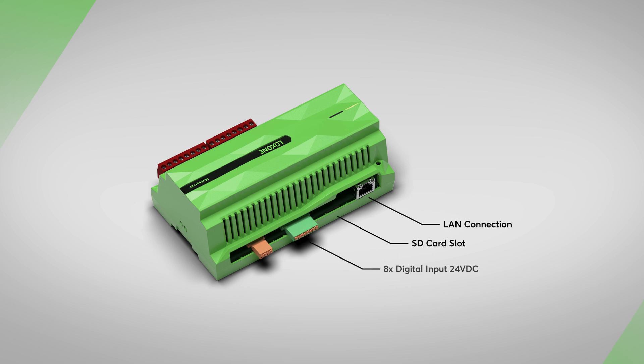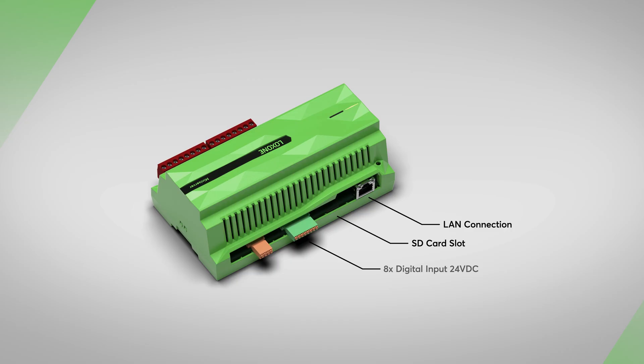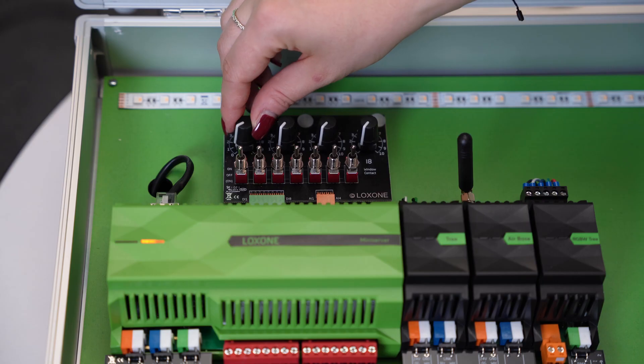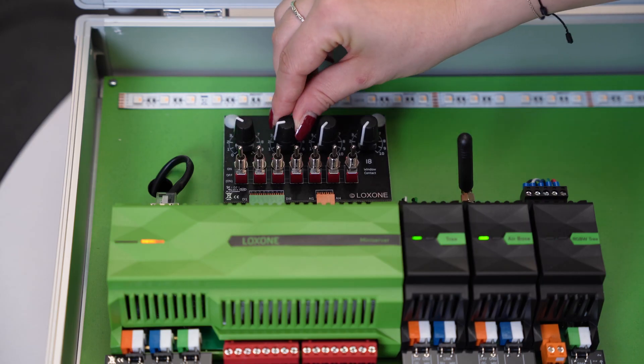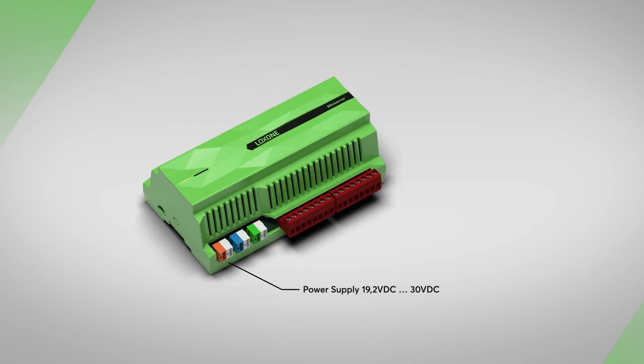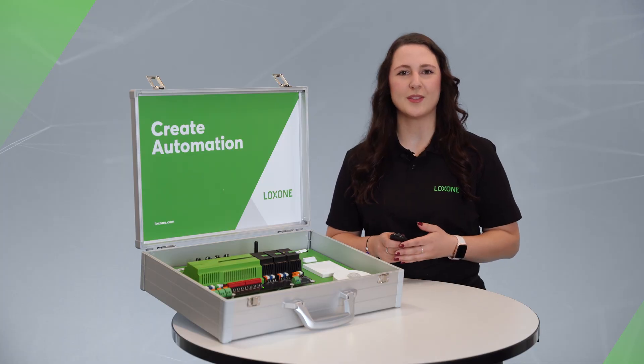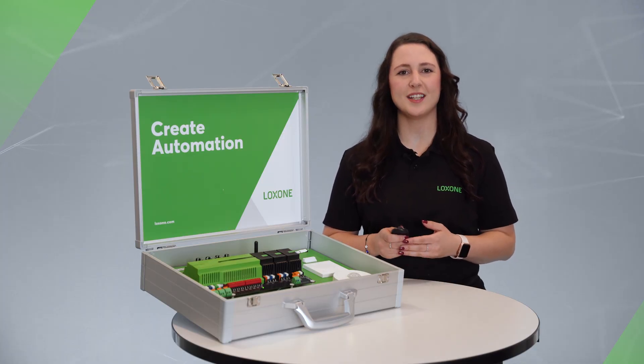There are also 8 digital 24V inputs on the top, which are assigned to a button switch combination. Next are 4 analog 0-10V inputs, each of which is assigned to a potentiometer to simulate sensors, for example. The orange-white clamp on the bottom supplies the mini server with an operating voltage of 24V DC. The blue-white clamp is the Loxone Link interface, so the mini server can be expanded with up to 30 extensions. The green-white clamp is a tree branch to connect additional Loxone sensors or actuators. We'll talk more about the link and tree technologies in just a moment.